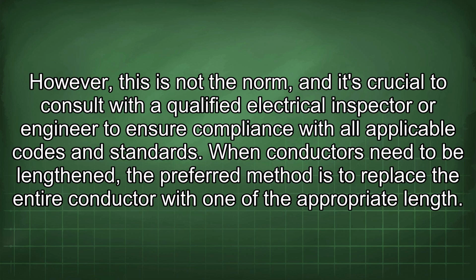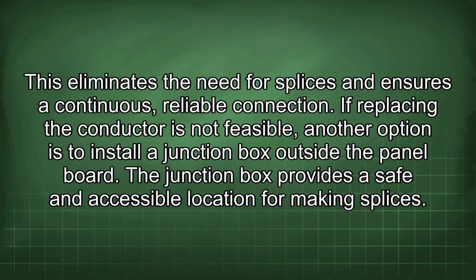When conductors need to be lengthened, the preferred method is to replace the entire conductor with one of the appropriate length. This eliminates the need for splices and ensures a continuous, reliable connection. If replacing the conductor is not feasible, another option is to install a junction box outside the panel board. The junction box provides a safe and accessible location for making splices.